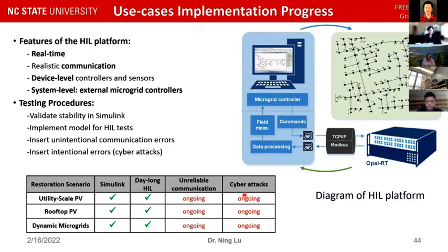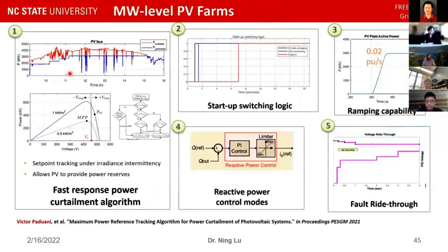So we can model several attacks. We do have this HIL with TCP/IP Modbus protocols, so we can see once a tower is down and the connected DER is down, what that would do to our control. We found that this kind of simulation is more realistic, because a lot of this control can't be assumed to be like an OpenDSS-based approach, where we send a control and the device receives it. In reality, we send out the control, and a device may or may not receive it immediately, usually with some delay.